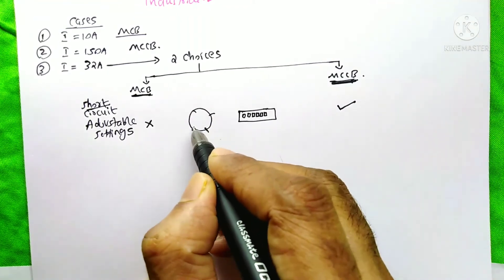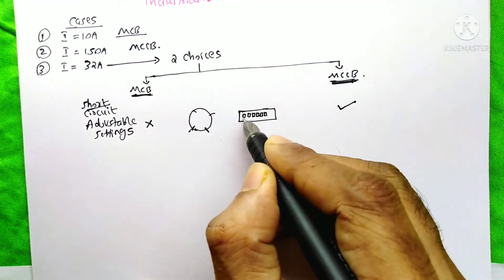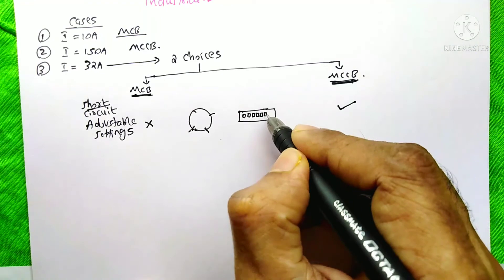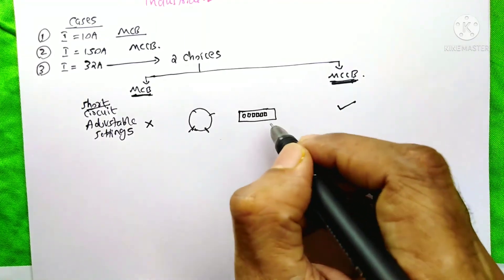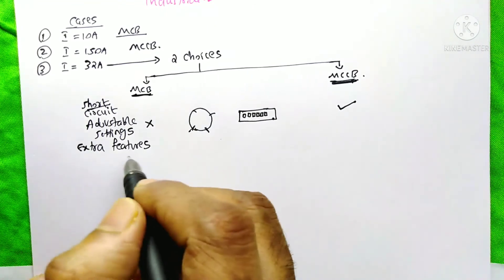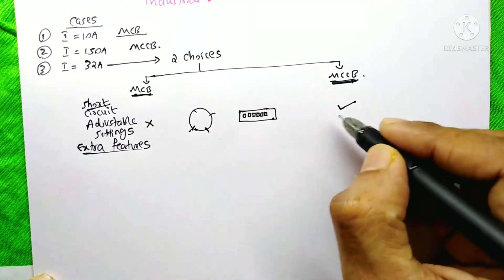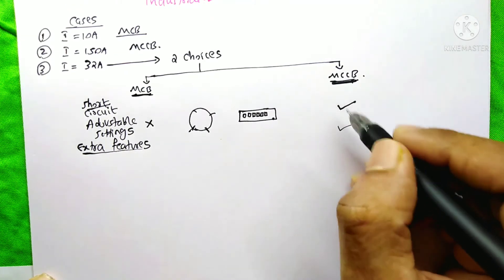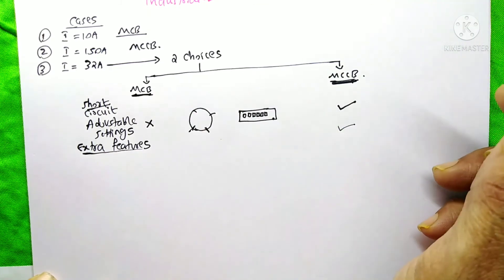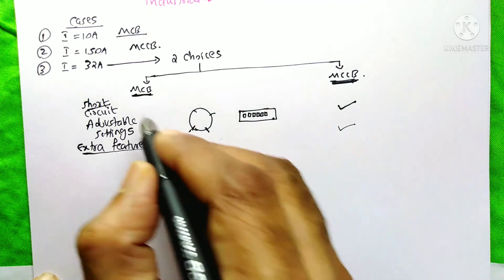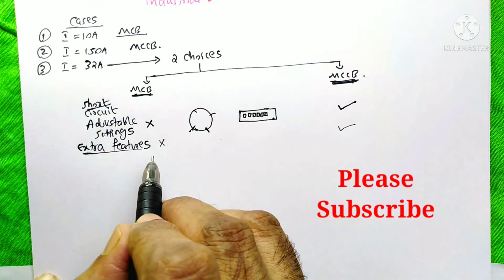Some companies offer a dial pad on top of the MCCB so you can select different current values, while others provide a series of knobs that you can move up or down to select different current ratings. If you need extra features such as over-frequency protection and under-frequency protection, you should select the MCCB, since it offers these extra features. The MCB does not have any such extra features.